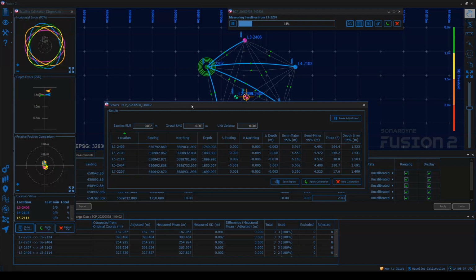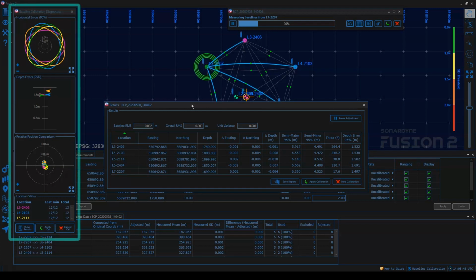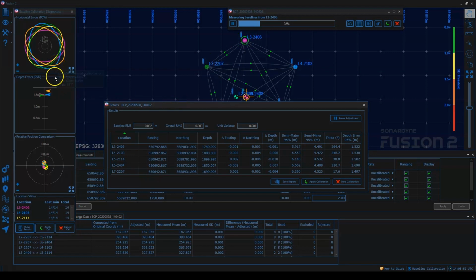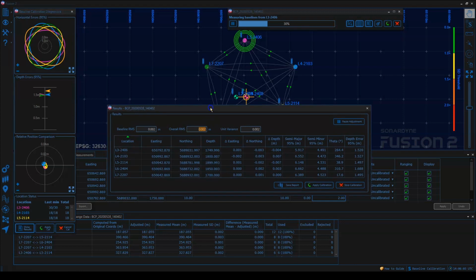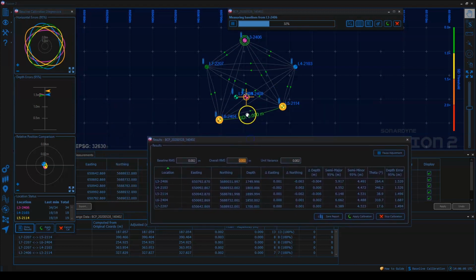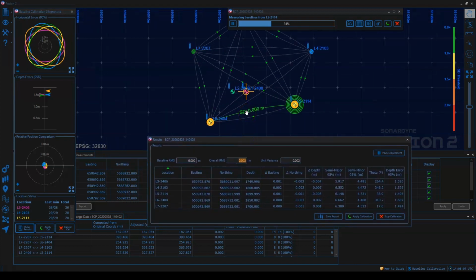This means that unlike Fusion 1, we don't have to spend long periods of time collecting data, only to find out later that it isn't usable. This information is also shown graphically in the baseline calibration diagnostic window, if you prefer to look at it that way. Baselines are collected using the same simultaneous process as Fusion 1, but the logic and the way the missed ranges are handled has been improved, so you should see a reduction in collection times in difficult environments.